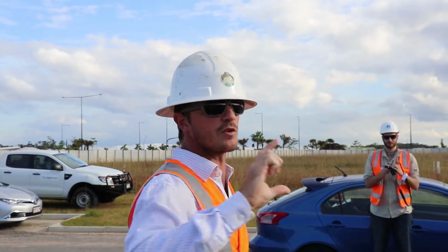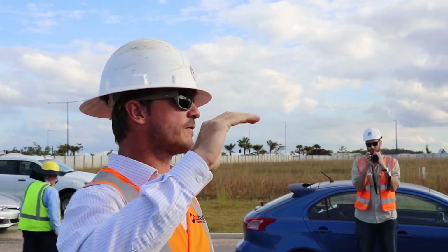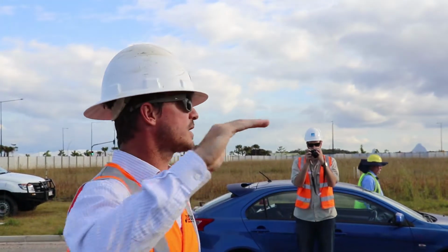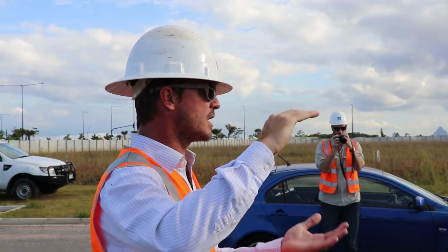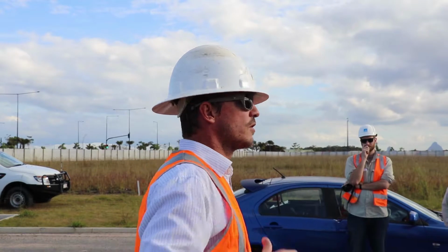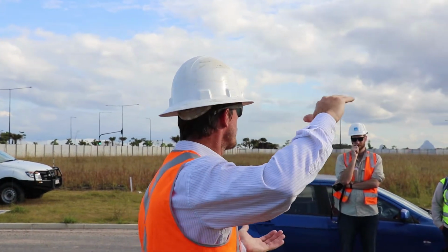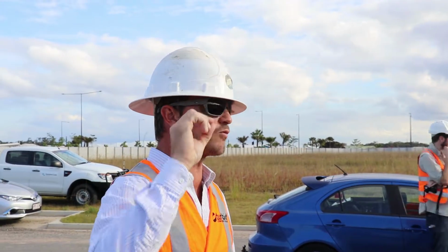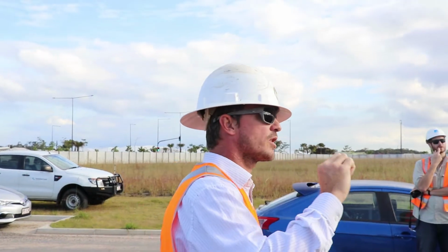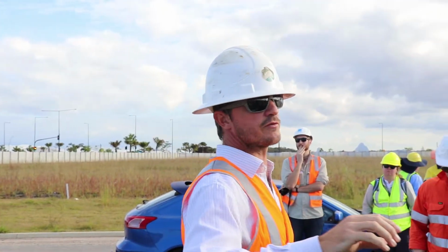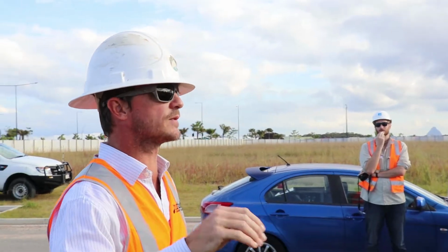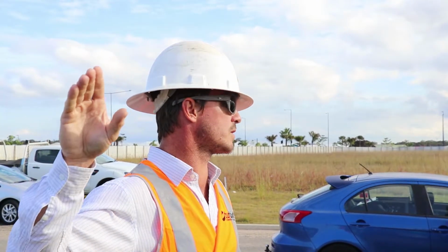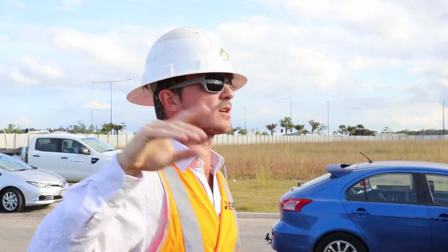And Kyle, you touched on what we call a window of opportunity, really, for the volume of water, what the effective dose rate range is going to be for that volume. So it may range between say 30 to 70 litres per megalitre of runoff, and you're still going to get effective treatment. Other sites may have a really small window of opportunity where you've got to get it pretty bang on, say 35 litres per megalitre or parts per million. So a flow-based system is going to give you that accuracy, but the downside is they cost more.